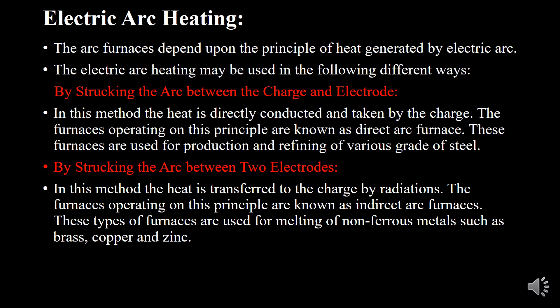The second method is by striking the arc between two electrodes. In this method, the heat is transferred to the charge by radiation. The furnaces operating on this principle are known as indirect arc furnaces. These furnaces are used for melting of non-ferrous metals such as brass, copper, and zinc.